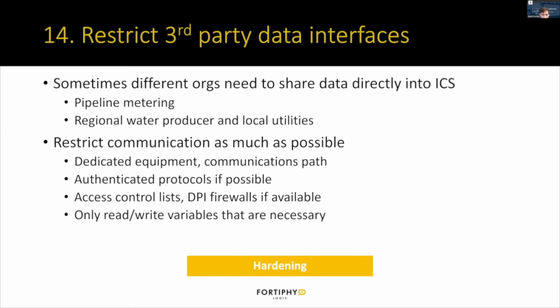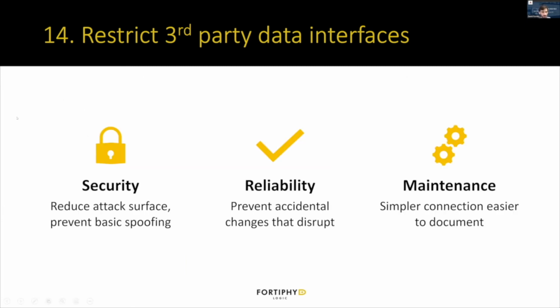So that means having dedicated equipment and communications paths, using authenticated protocols if possible, using access control lists and firewalls if available, and only giving the other party read and write access to absolutely what they need, not anything else. For security, this helps reduce the attack surface, reduce the options available for an attacker to cause problems, and helps prevent some basic spoofing attacks. For reliability, it helps prevent accidental changes that will disrupt the process. And for maintenance, it's a simpler connection that's easier to document and keep track of over time.